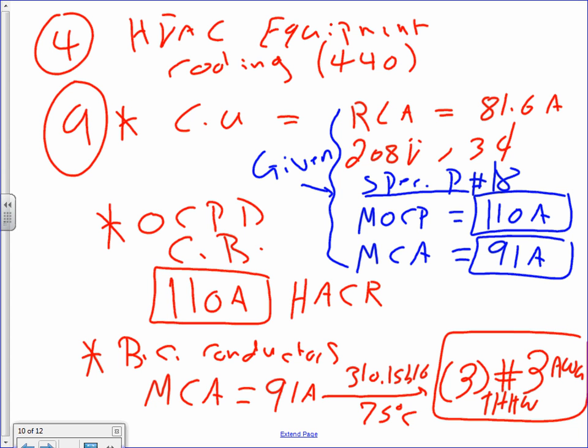Any question, guys, about this? Let me repeat myself one more time. For heating, ventilation, and air conditioning equipment, you use the nameplate. If it's a condensing unit, you always use the nameplate. On the nameplate, it says rated load amps, 81.6 amps. It says 208 volt 3-phase. And the specification says maximum overcurrent protection device 110 and minimum circuit ampacity is 91 amps. 91 amps, that's right on the spec.